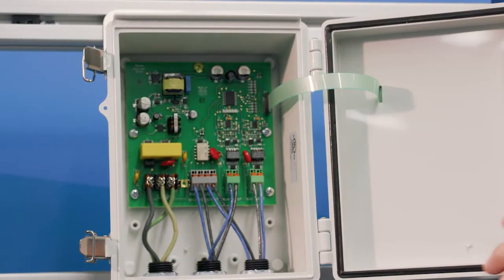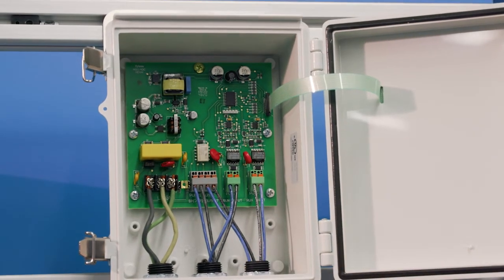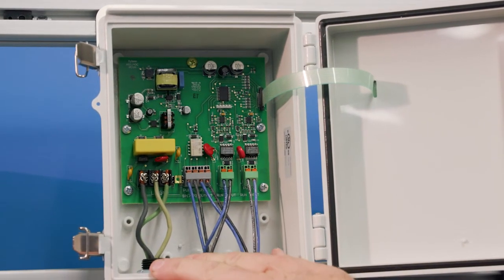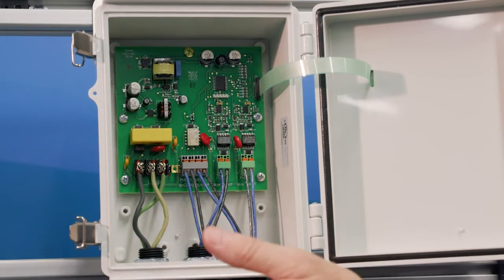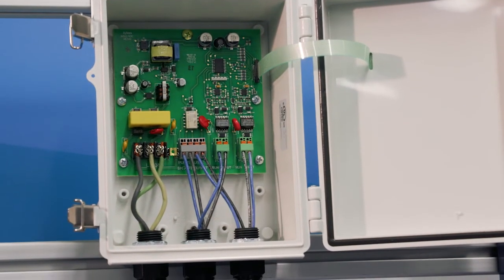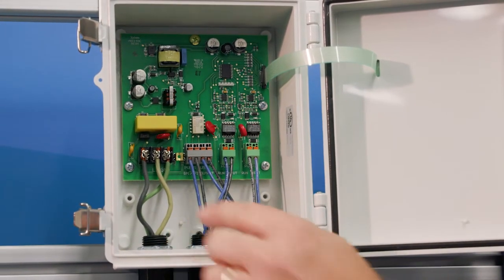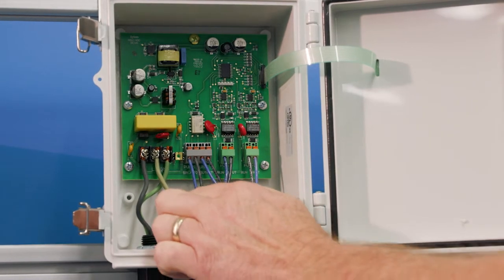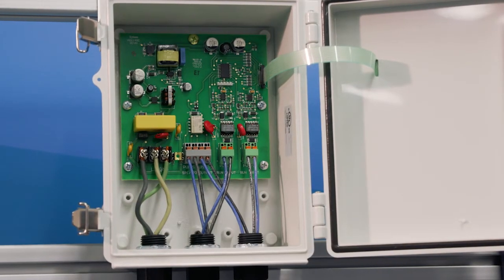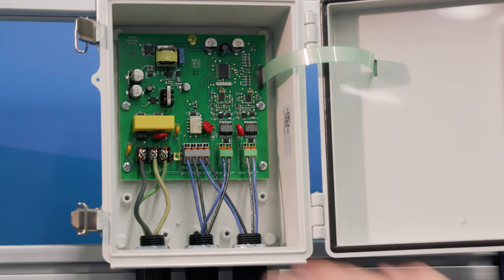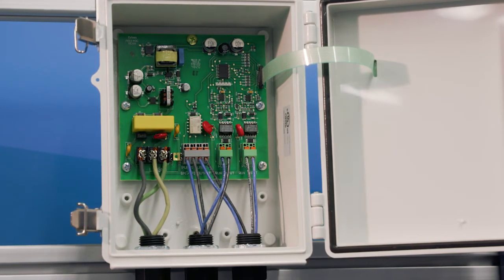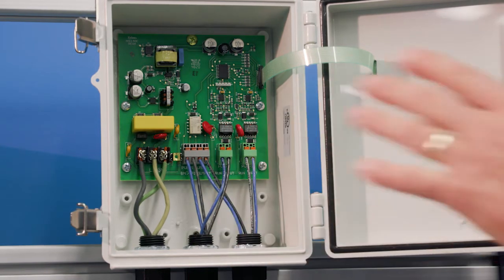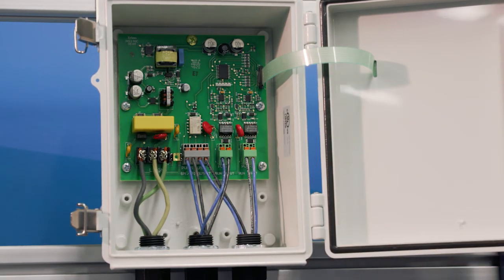So we do need separate power for this panel. We can bring in 115 or 120 or 240. In this case here, we're just using 120 power coming in. So you have those 2 options to provide power to your alternator. So next, let's take a look at the wiring. Again, this is all pre-wired for lead lag alternation based on runtime.